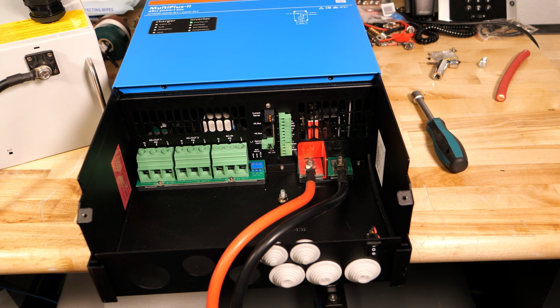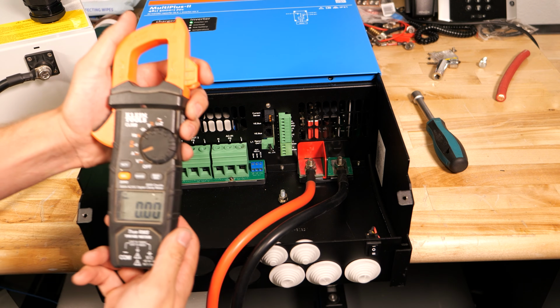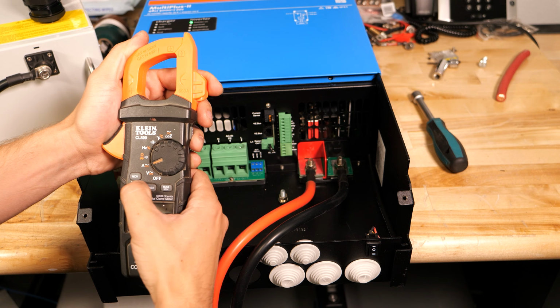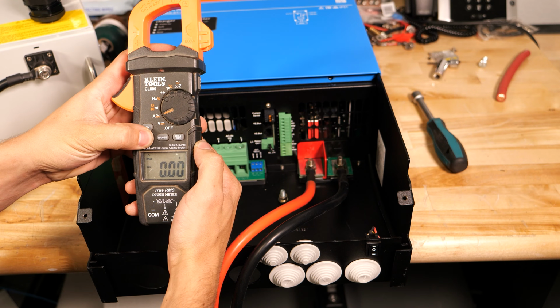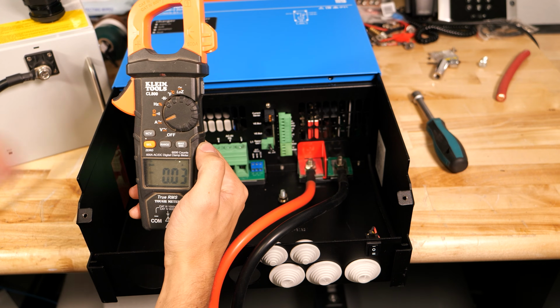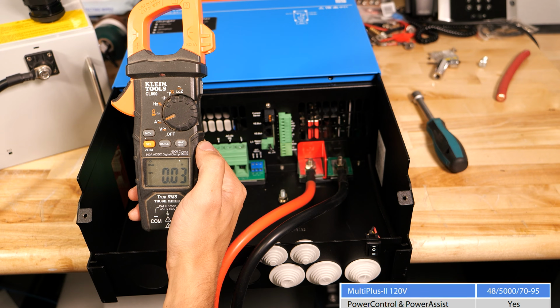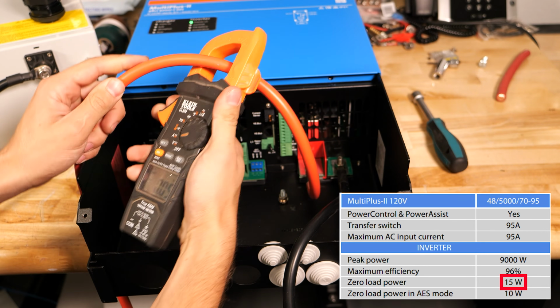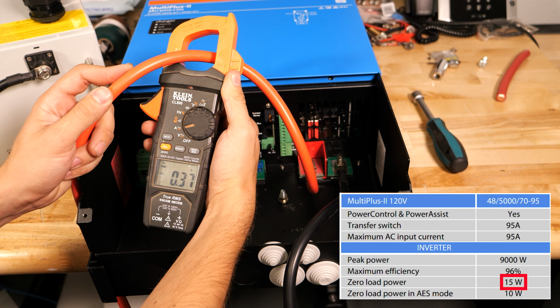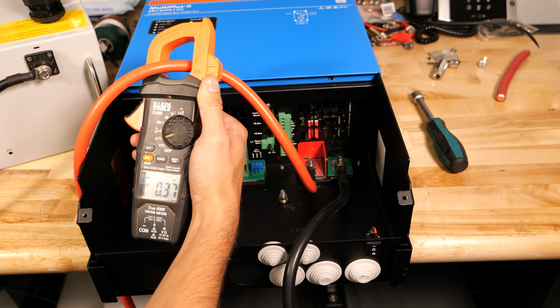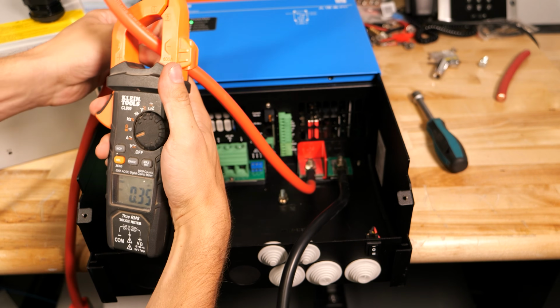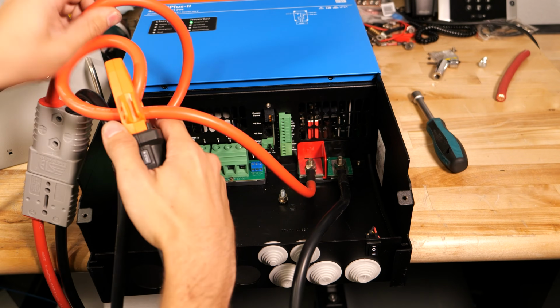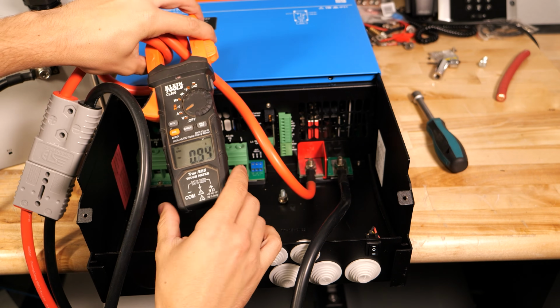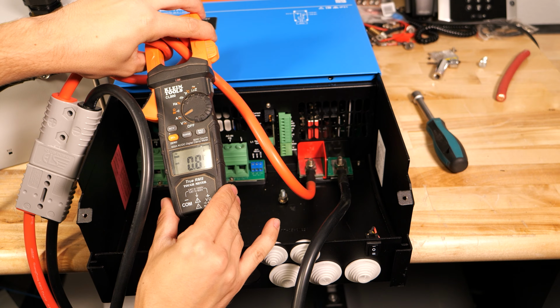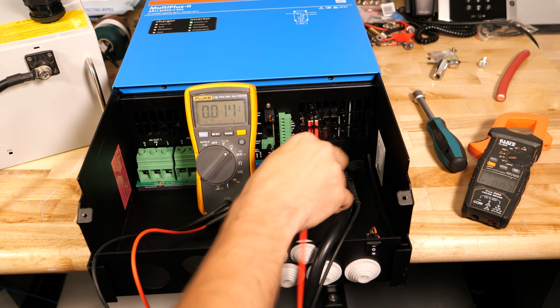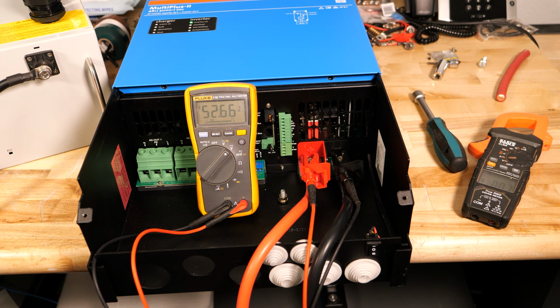Now, one of the other disadvantages to low-frequency inverters is their idle consumption. So I have my Klein Tools CL800 clamp meter, this one has been all over and back. I'm going to zero it out here. I hope you guys can see that, but it's at 0 amps. Now, this inverter advertises a really low idle draw, it's less than 20 watts, I forget the exact spec, but if we clamp onto this, I have 0.38 amps. Now, these clamp meters are not very accurate at this low of a current rating, so what I'm going to do is actually wrap my cable around here 3 times, and that'll give me 3 times the current reading. So if I measure, that's about right, 0.90, so I have about 0.3 amps. And if I use my Fluke meter real quick to measure the voltage, 52.6 volts.